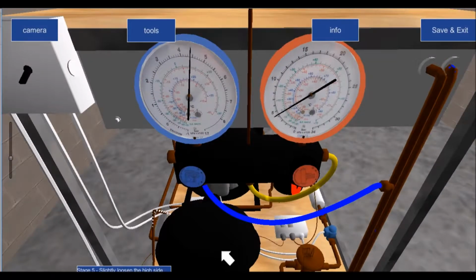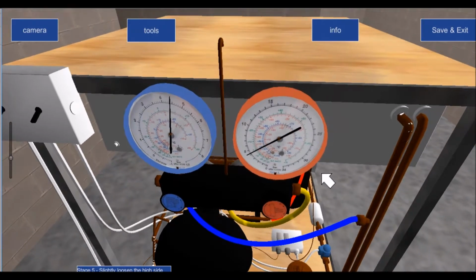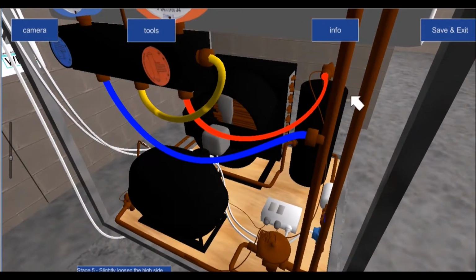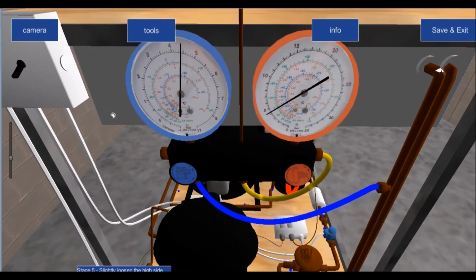But as I was trying to show you, in our own simulator here, because we have no gas, we are not exposed to the high side of the system. We have no gas in this hose line because we didn't crack our valve. But we do have gas in this hose line because we fitted it to a Schrader fitting, which acts in the same way as a car tire or a bicycle tire. Because we were able to open this, we allowed the refrigerant to enter into the manifold. And then when we opened this, we allowed the refrigerant to travel into the high side of the system, into the red hose, and this is where you're getting your equalization taking place.